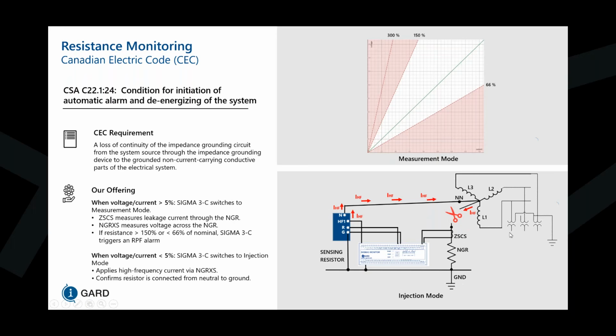Now, a lot of customers have YYPTs where the primary is grounded. And our signal is not impacted by YYPTs where the primary is grounded. PTs in general have a very high impedance when it comes to AC signals. When it comes to DC resistance though, these types of PTs have a lower resistance. So comparably, the AC resistance would be in the mega ohms, but in the case of a DC resistance, it could be in the range of 100 to 300 ohms, or even less than that. It depends on the manufacturer. But that's why we chose the high frequency signal.